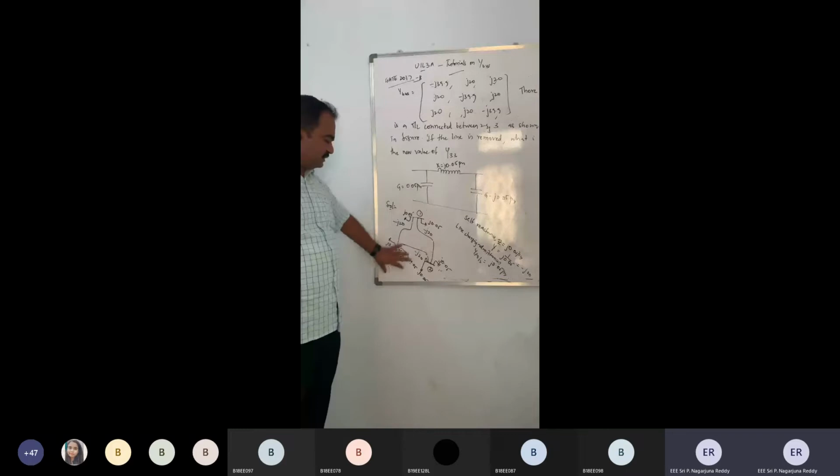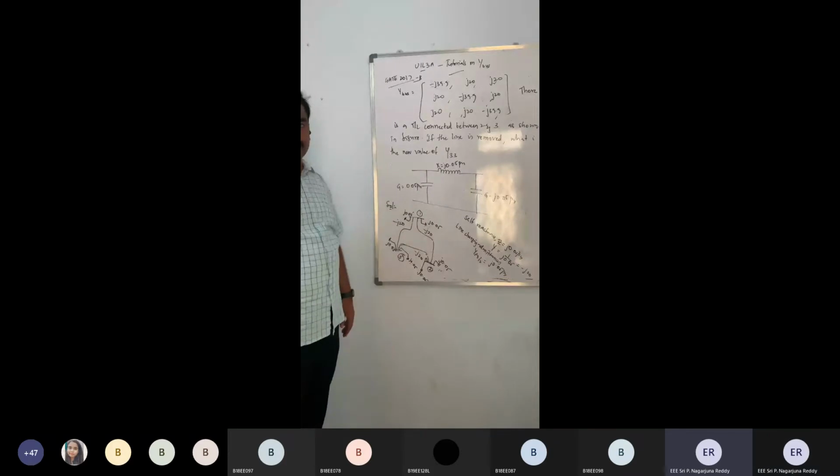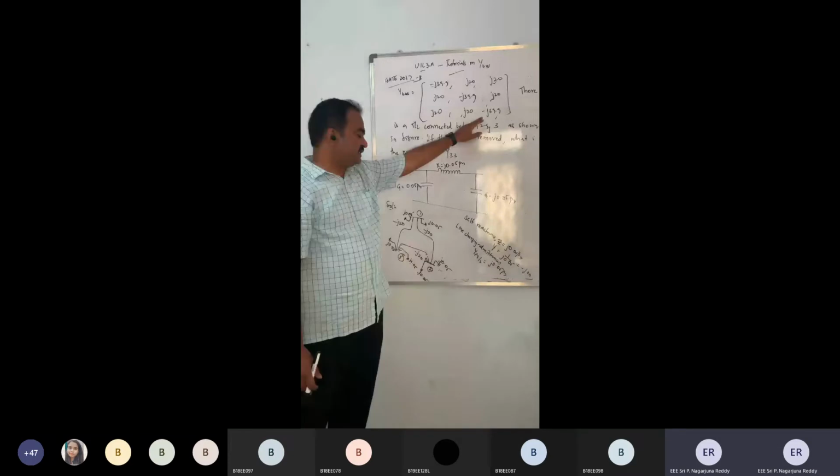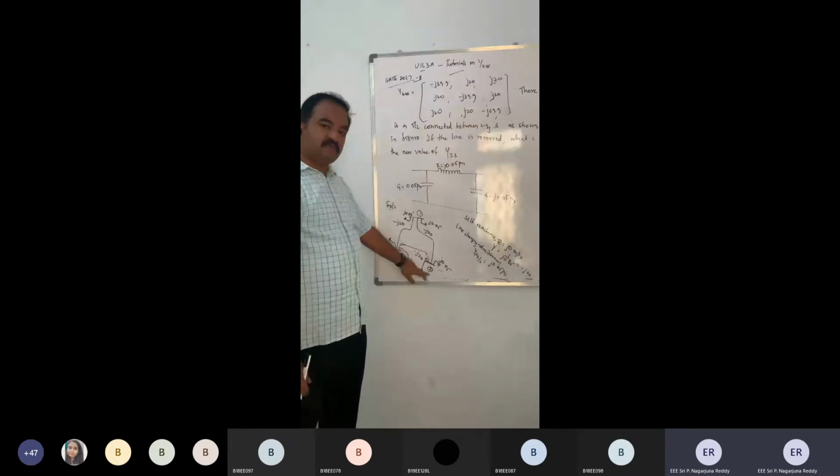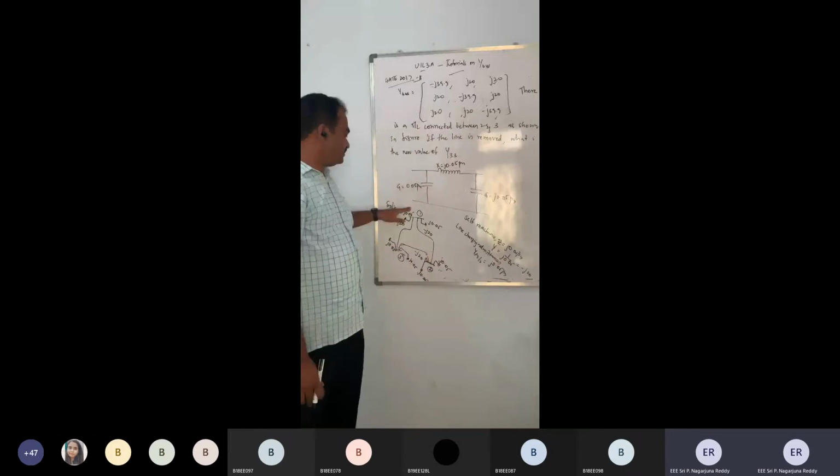So now I feel that all the transmission lines are very similar, and each has similar line charging admittances. I feel that this is the problem. Okay, now you can verify it. What is the summation of all these elements at bus 3? It is minus J39.9, satisfied. At bus number 2, minus J39.9, satisfied. Bus number 1, minus J39.9, satisfied.